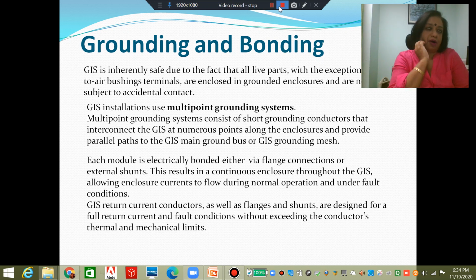So when we talk about the grounding issues in GIS, we are at an advantage because GIS is inherently safe to use. All the live parts are inside the enclosure, and the enclosure in the first place is a grounded metal enclosure. So we don't really have any access to live paths from outside. Of course, there are the bushings to air terminals from inside to outside. There are bushings which connect to the outside. Apart from that, the possibility of accidental contact is minimal.